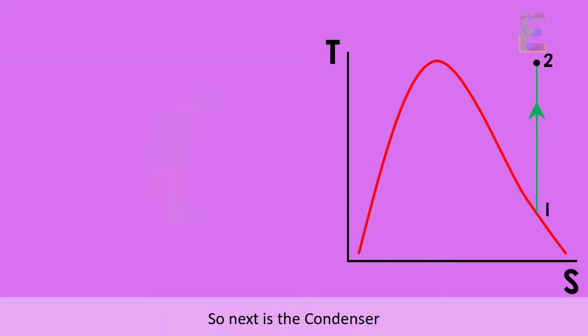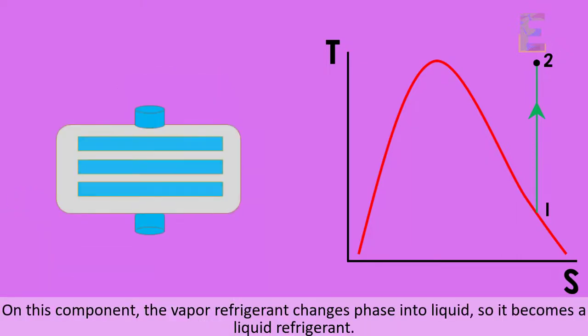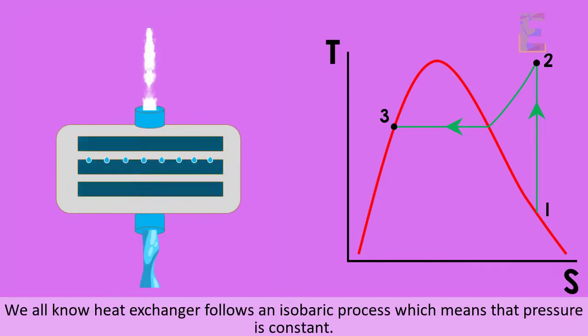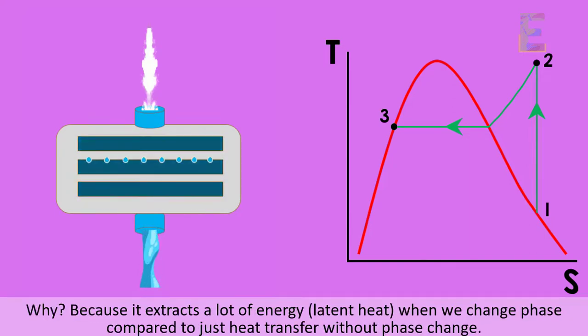So next is the condenser. On this component, the vapor refrigerant changes phase into liquid. So it becomes a liquid refrigerant. Its temperature decreases, but the pressure remains the same since this is a heat exchanger. We all know heat exchanger follows an isobaric process, which means that pressure is constant. The main purpose for this component is through condensation, we remove a larger amount of heat from the refrigerant. Why? Because it extracts a lot of energy or latent heat when we change phase compared to just heat transfer without phase change.